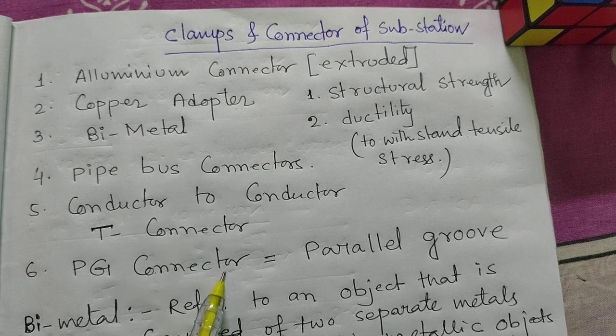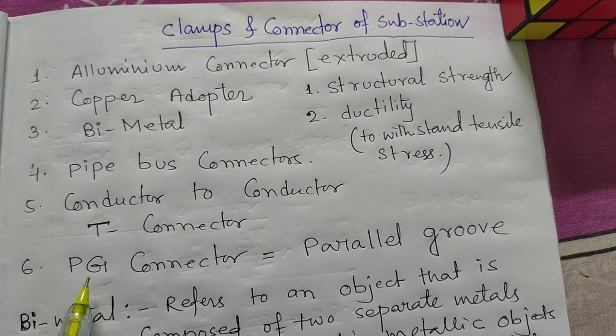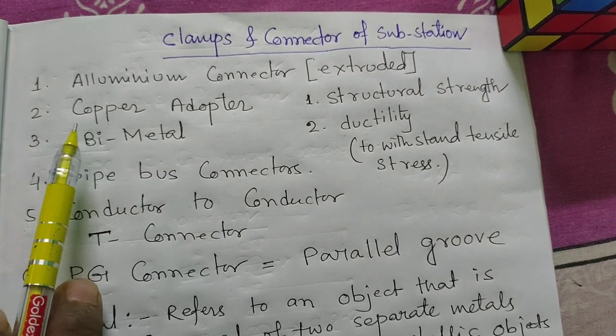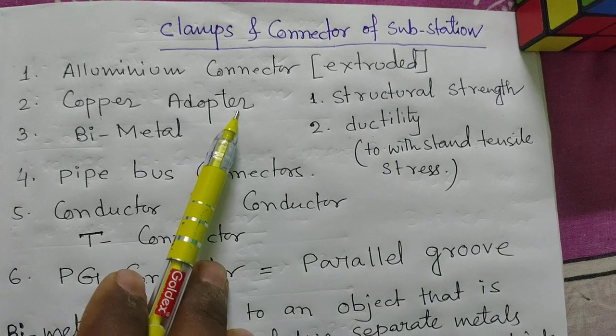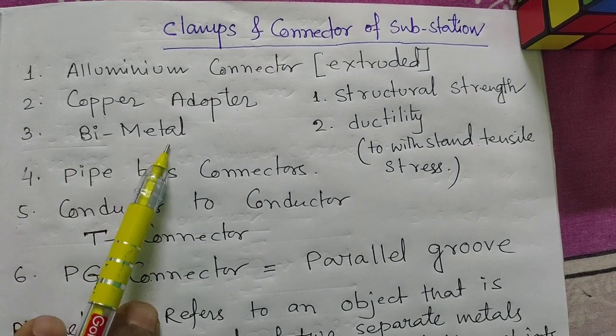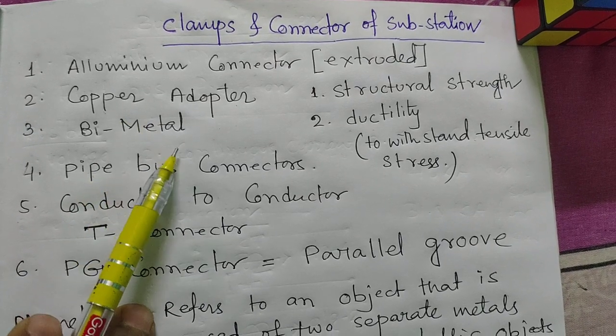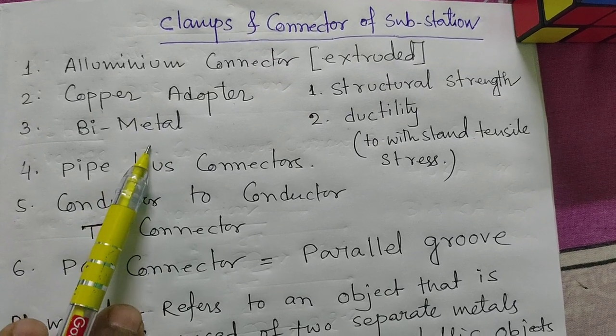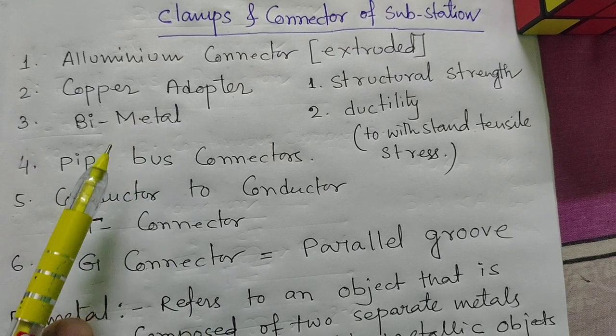The connectors we use include copper adapters, bimetals, pipe bus connectors, conductor-to-conductor connectors, T connectors, and PG connectors. The full form of PG is Parallel Groove connectors. Copper adapters are being used at 33 kV substations, and bimetals are used at 132 kV, 220 kV, 400 kV, and 33 kV levels.